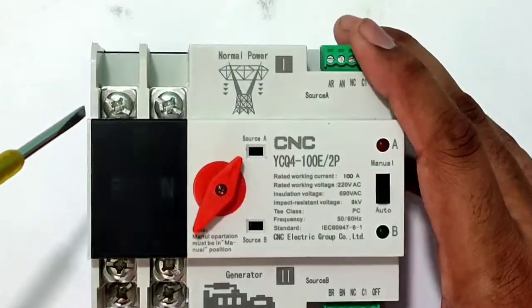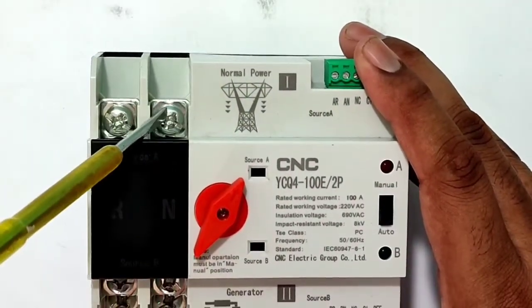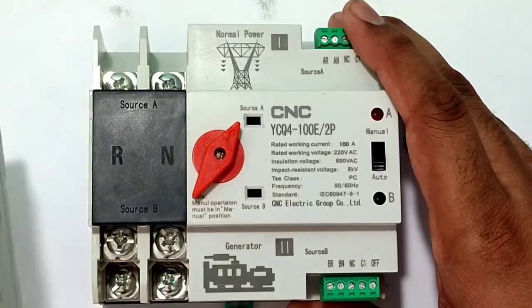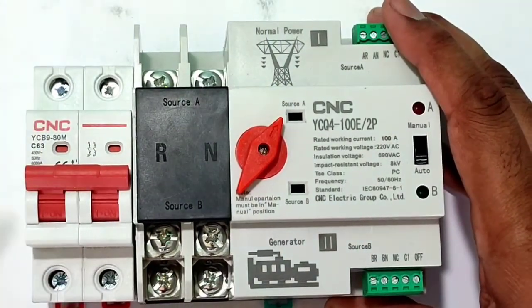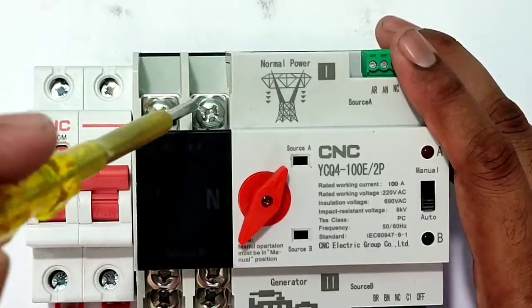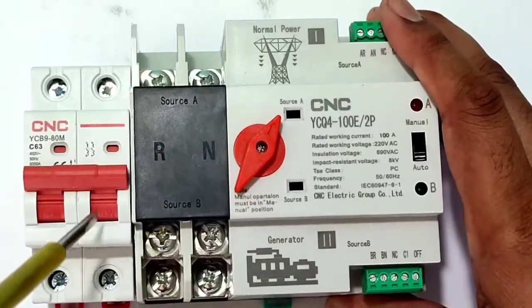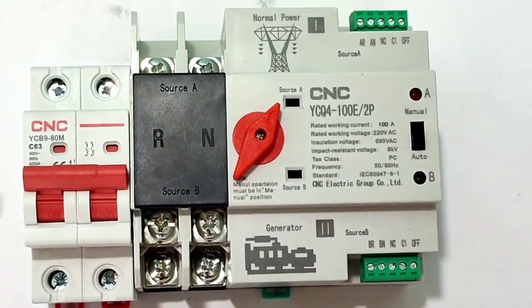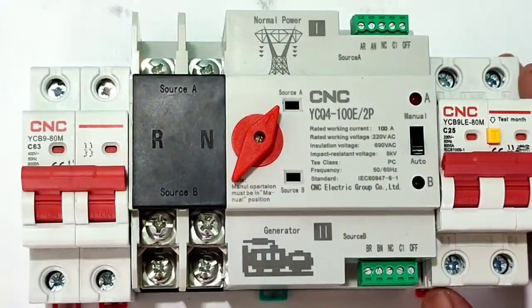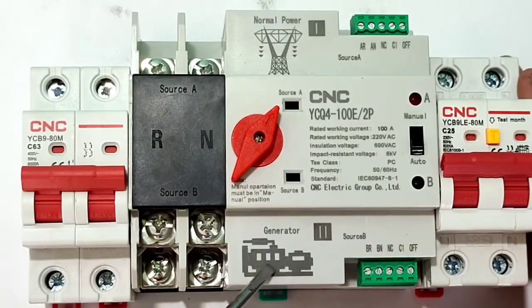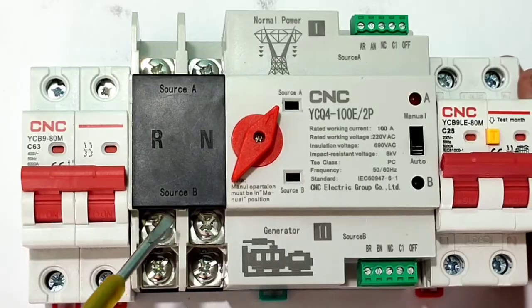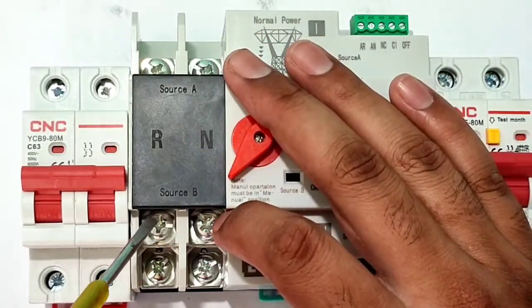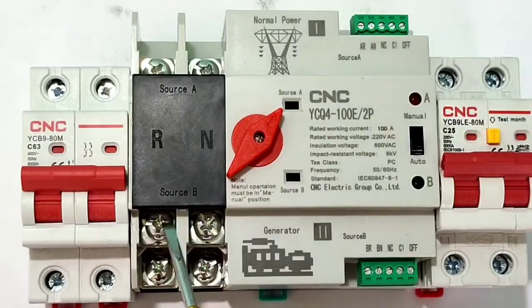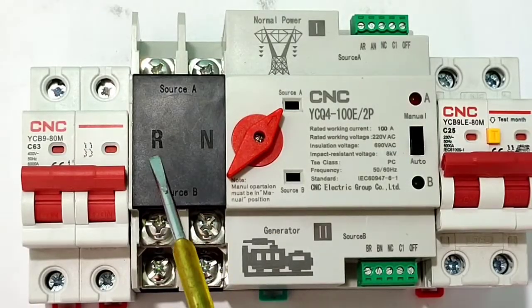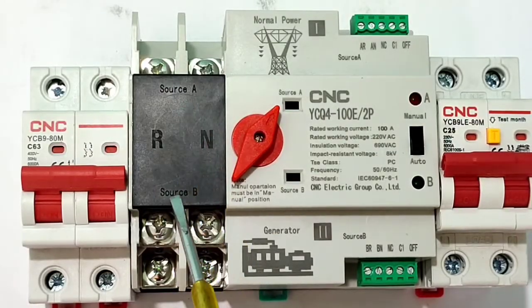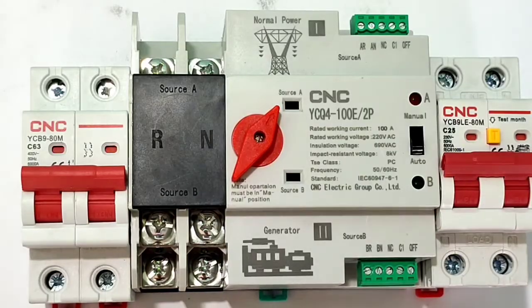Now you can see here, for normal power supply we need to connect our main power supply. The main power supply we connect through this circuit breaker. For normal power supply, we need to connect a phase and neutral here. And if you have source B, for source B, the generator power supply or inverter power supply, we connect this circuit breaker. You can see here the generator power supply. So we connect the generator power supply output to source B, here phase and neutral. So we have two power supplies, source A which is the main power supply and source B which is the generator power supply.